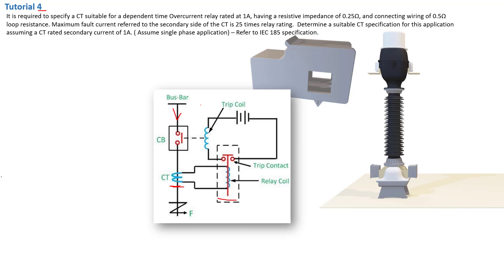The 1 amp of current will then energize the coil of our overcurrent relay, and that coil will trip the trip contact. That will then complete the circuit for the DC power supply, and that current will flow into a coil which will be energized. As a result, it will pull another trip contact, releasing the circuit breaker and isolating the part of the circuit that is in trouble, hopefully isolating the fault in time to save our equipment and the personnel that may have been exposed to the fault.